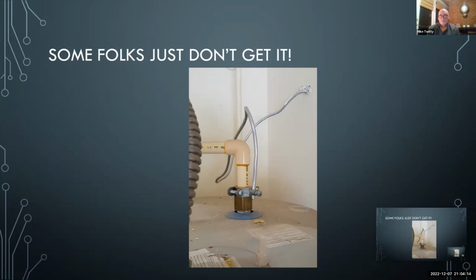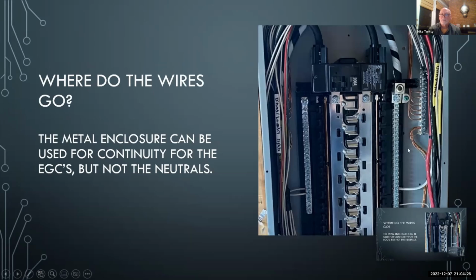They don't carry current in a normal situation, if there are no faults. But if you get something against this case, like this hot wire, a whisker comes off here and energizes this case, then, if it's a branch circuit, this equipment ground carries the current back to the neutral, back to the transformer to complete the circuit and trip the breaker. It's got to have that complete loop to trip a breaker or blow a fuse. So they do carry current when there's a fault, and that's why there are size requirements for equipment grounds, just like there are for other conductors, depending on the amp rating of what they're protecting.